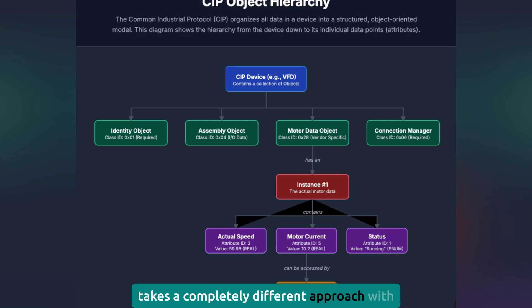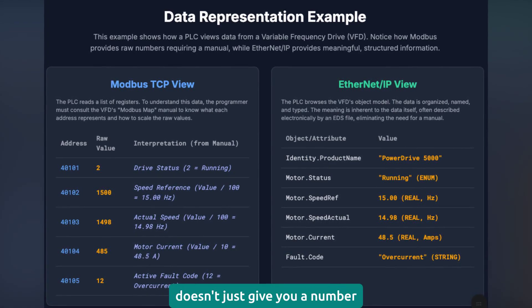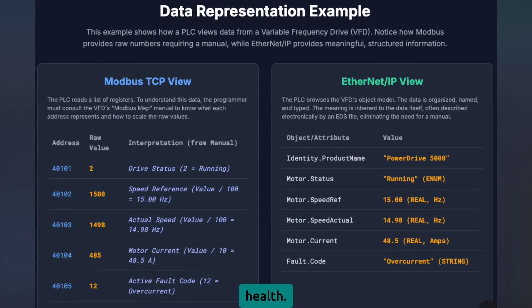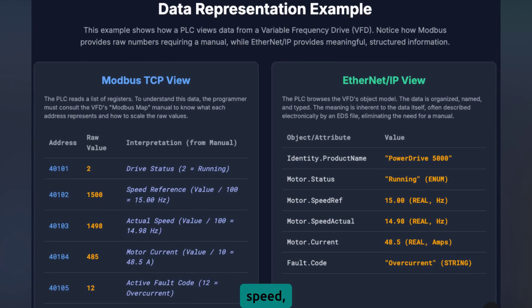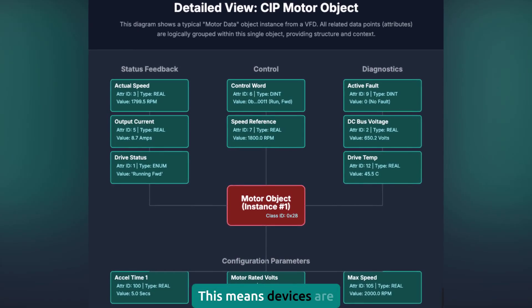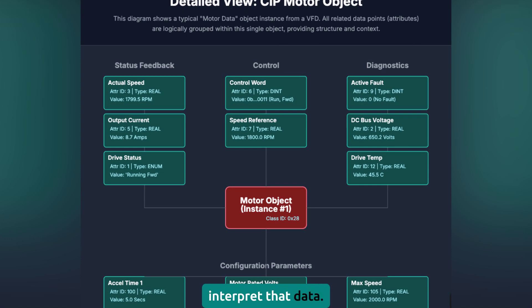EtherNet/IP takes a completely different approach with the Common Industrial Protocol Object Model. Instead of generic registers, it organizes data into objects that represent real-world things. An analog input object doesn't just give you a number — it gives you the engineering units, scaling information, alarm limits, and diagnostic information about sensor health. A motor object includes speed, torque, current, fault status, and operating hours, all organized together. This means devices are self-describing. When you connect a new EtherNet/IP device, your system can automatically discover what it is, what data it provides, and how to interpret that data. No more guessing what register 41157 means — the device tells you its inlet pressure in PSI with a range of 0 to 300.